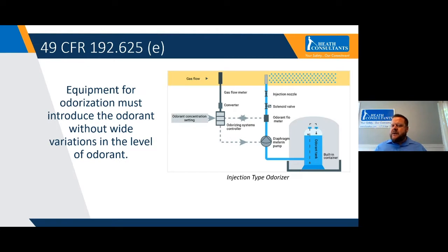In the case of over-odorization, you possibly don't even have a gas leak, but the odorant is so strong that it leaches out of the system, and customers think there's a gas leak when there may not be one. In the case of under-odorization, you could possibly have a gas leak, but there's not enough odorant for the customer to smell it. That can also be dangerous because you have undetectable leaks around you.